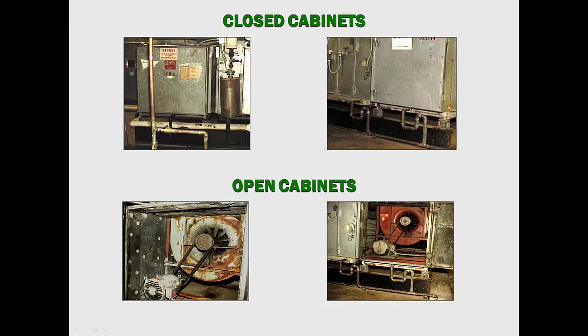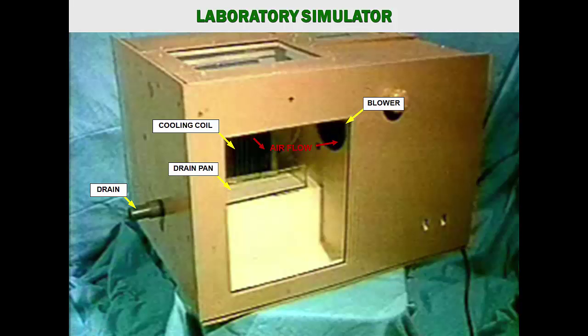Typically, what they see during operations are units like those shown in the top photographs. Only when the cabinet is open can the damage be revealed, as shown in the lower photographs. But even then, the causes are not apparent. But they can be illustrated vividly using laboratory-simulated air handlers with transparent panels. These simulators allow building owners and other concerned parties to see and understand how trap failures cause damage and contamination to their air handlers and buildings.